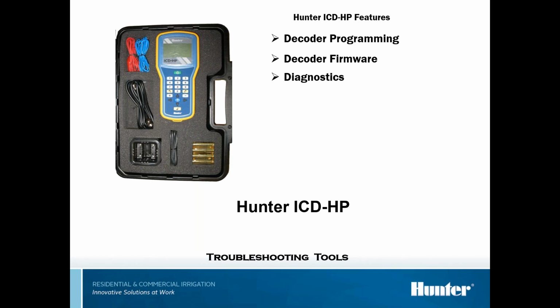And then from there, you can take it out to the field and you can update decoder firmware. You can do other diagnostics, turning stations on, turning stations off. You can read voltage. You can check your milliamps. There's a lot of good stuff with the diagnostics, and you can see the station test. You can also do a clik or flow sensor test. You can treat it as a volt or an amp meter where you can see your exact voltage on your line.